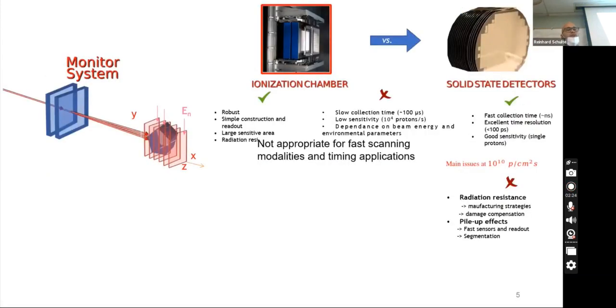Today, the ionization chambers are the ones monitoring the system. They are robust, have simple construction, and readout, have a large sensitive area, and radiation resistance, but they suffer from slow collection time, low sensitivity, and dependence on beam energy and environmental parameters. So, due to the challenge of pencil beam scanning, these devices are not appropriate for fast scanning modality and timing application.